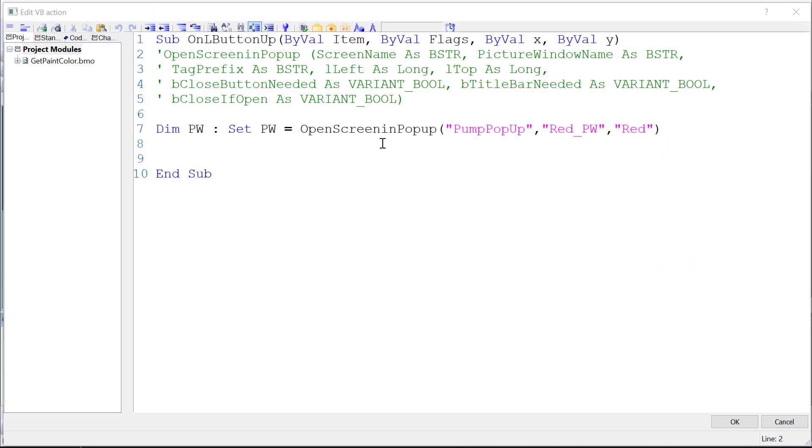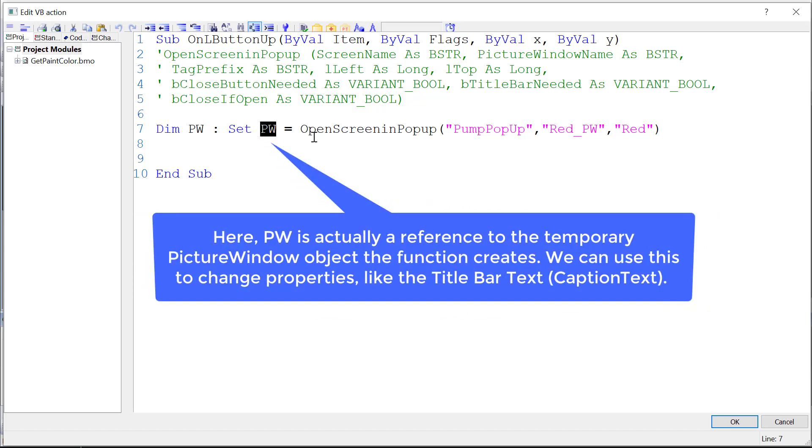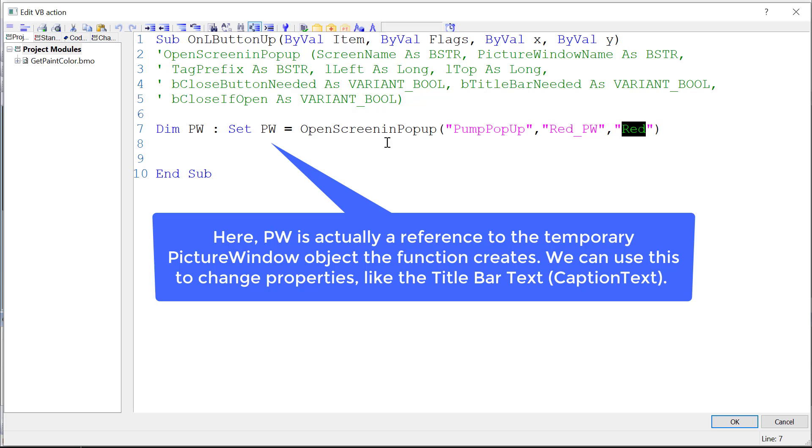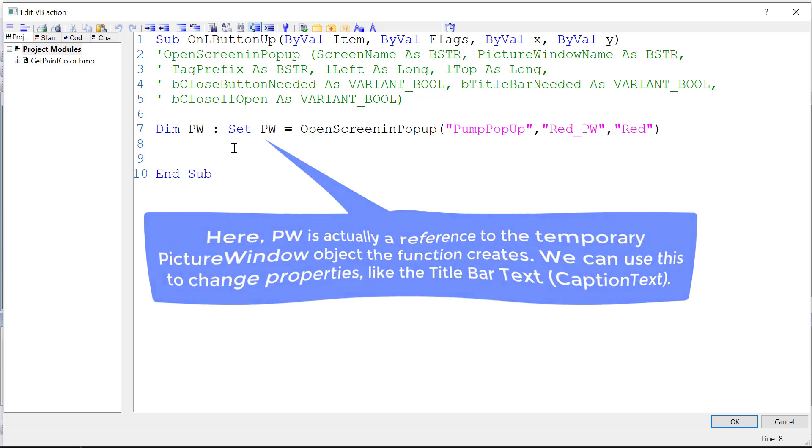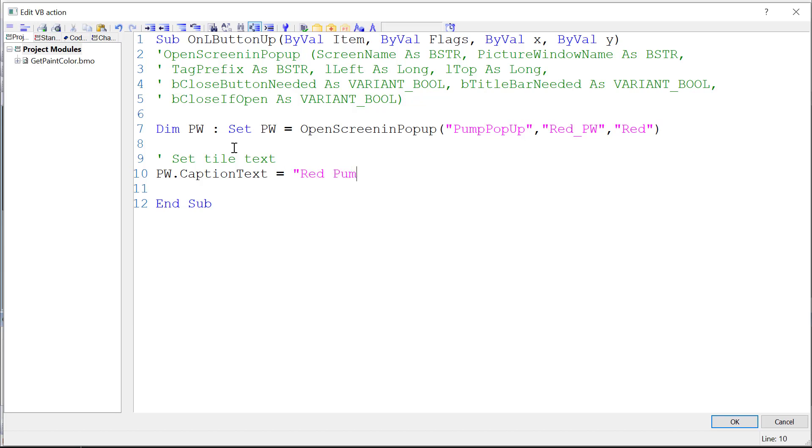If we want to make changes to the window, like set the title bar text, it doesn't explicitly say it in the help file, but this variable that we use the set command with is actually a handle to the new picture window named redpw. It is showing this picture and the tag prefix is set to this. So if we want to set our title, I can just say set title text pw dot the caption text is the property that defines the text that is in the text label of the window. I could just do something like red pump for now.